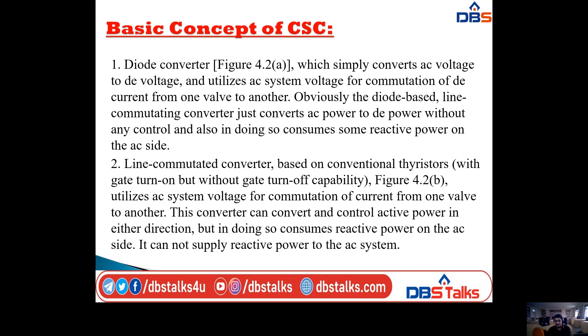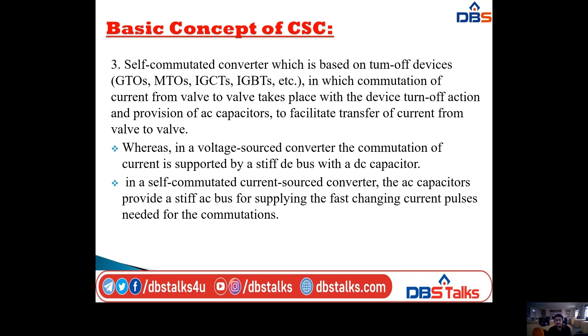Coming to the second type — the line-commutated converter — it is totally based on conventional thyristors with gate turn-on but without gate turn-off capability. It utilizes AC system voltage for commutation of current from one valve to another. This converter can convert and control active power in either direction, but in doing so consumes reactive power on the AC side. The line-commutated converter cannot supply reactive power to the AC system; it only consumes reactive power on the AC side.